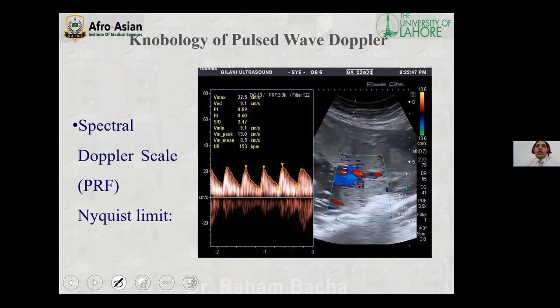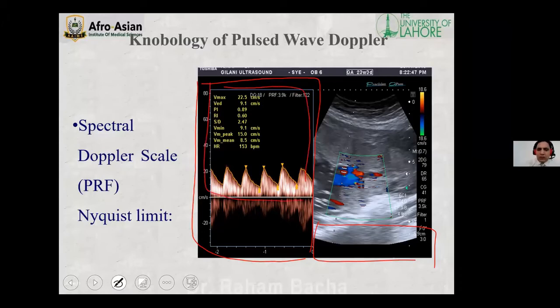Then spectral Doppler scale or PRF. So you can see this is a spectral Doppler window. I told you at the start that this spectral Doppler window could be at the base or at the side of the grayscale image. This spectral Doppler window has some other things. It has been divided into 2 channels by this baseline. And there is a graduated line beside this spectral Doppler window, and this graduated line is called the spectral Doppler scale, and the extreme point of this scale is called the Nyquist limit.